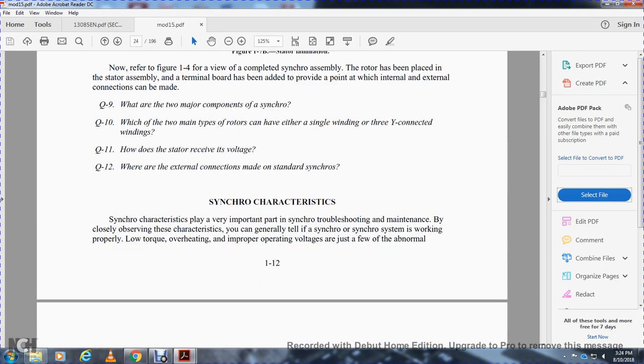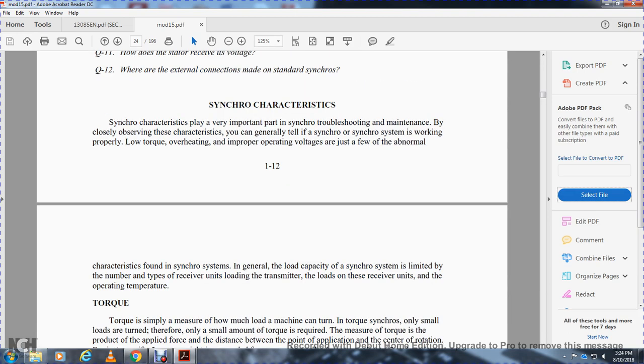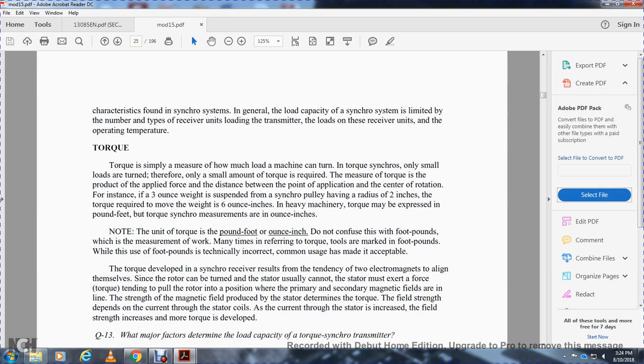Synchro characteristics: several characteristics play a very important role in synchro troubleshooting. Low torque, overheating, and improper operating voltage are just a few of the abnormal conditions found in a synchro system. The general load capacity of the synchro system is limited by the number and type of receivers. The operating torque is simply a measure of the force required to turn the synchro — only a small amount of torque is required. Torque is measured as a force applied at a distance, for example, in ounce-inches or pound-feet.